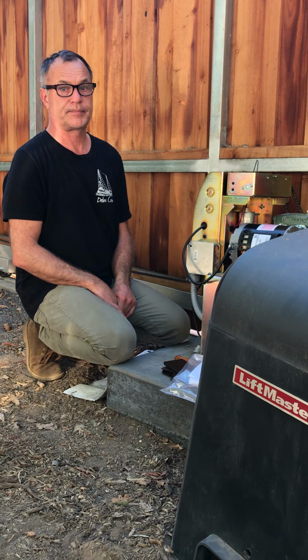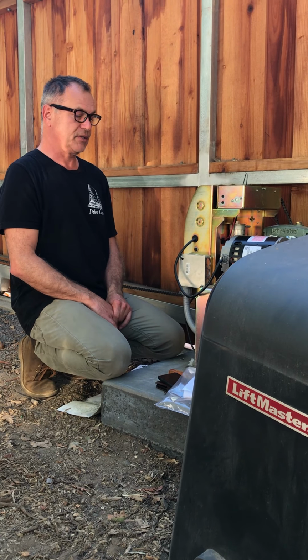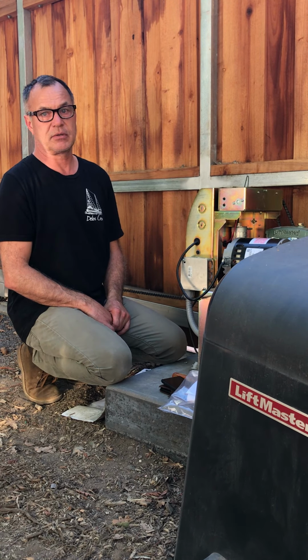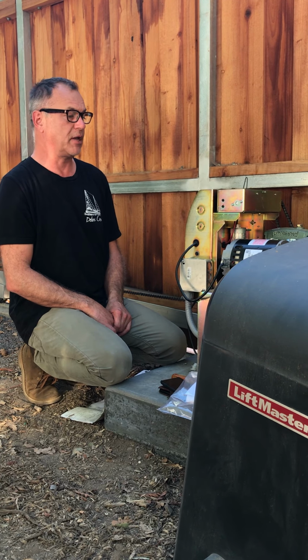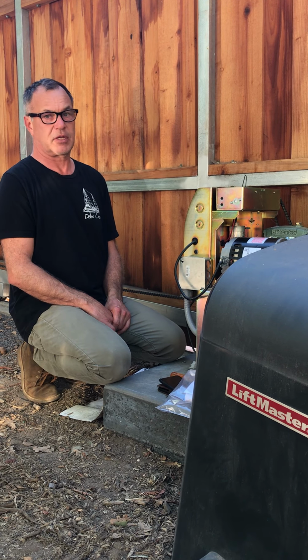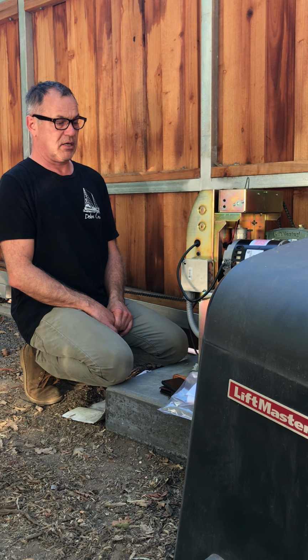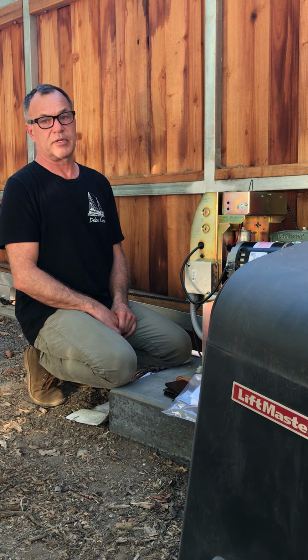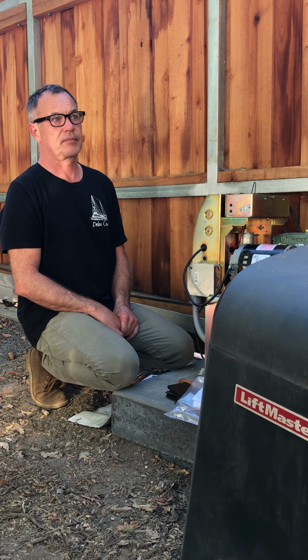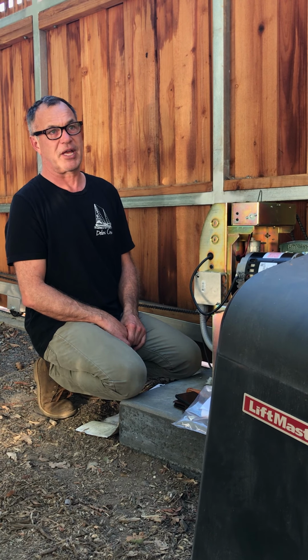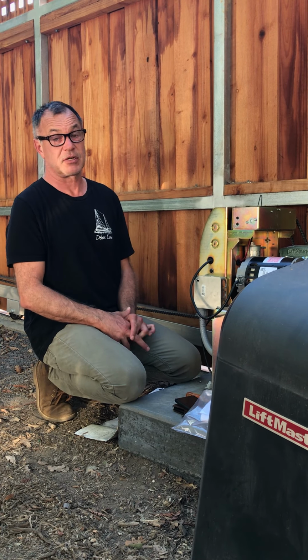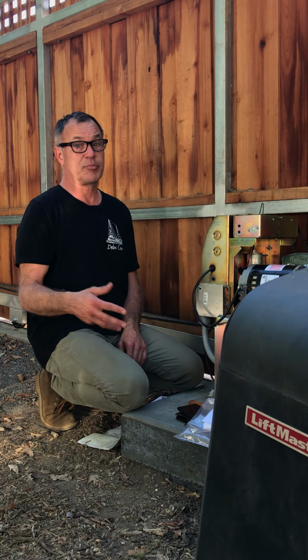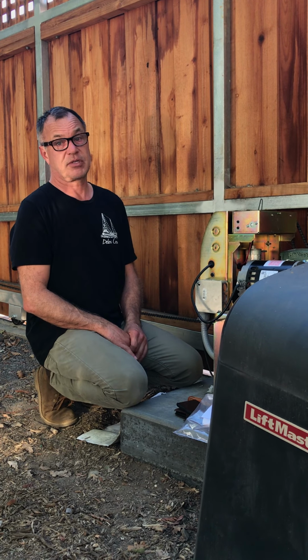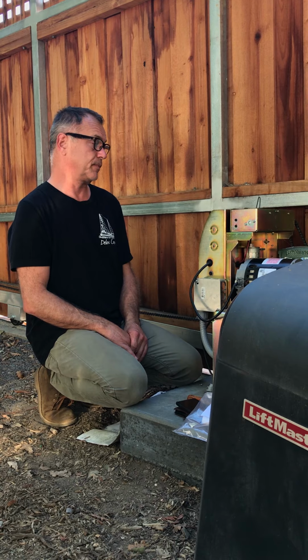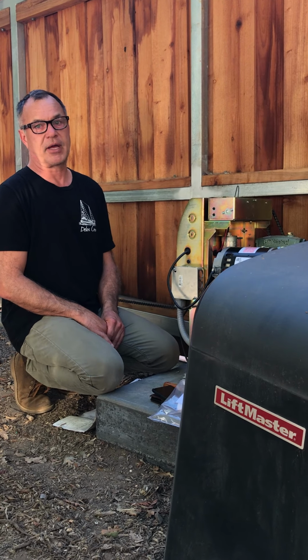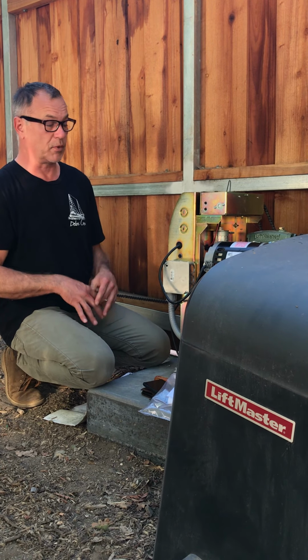What other parts have you replaced so far? So we've replaced the start capacitor with a brand new capacitor, just to make sure that the surge of current to the motor isn't being too high because the capacitor is bad. So we switched the start capacitor, and we're confident that that's not the problem. We've also switched the power board out. So we've mailed back the power board, they gave us a new one, and we wired it all back up.